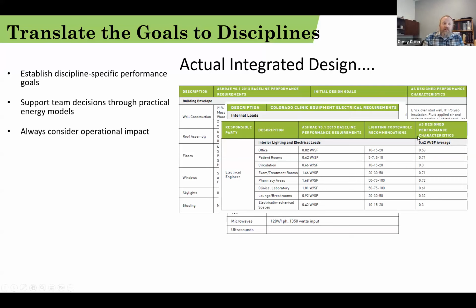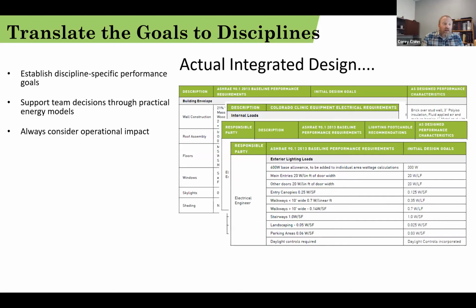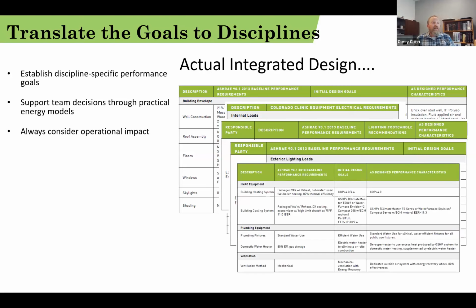Huge win on this project. We actually got it designed at 0.42 watts per square foot average, which is incredible. We included the site lighting. We looked at the HVAC equipment, and we assigned goals to every discipline and each primary component that contributes to energy consumption in a building.